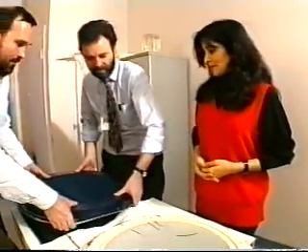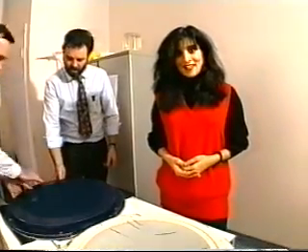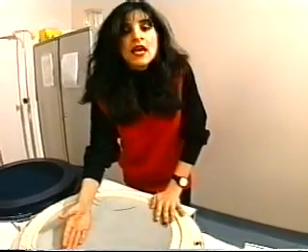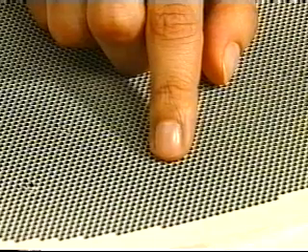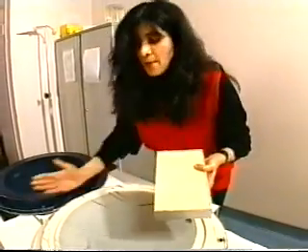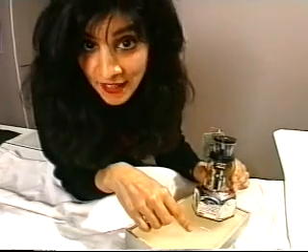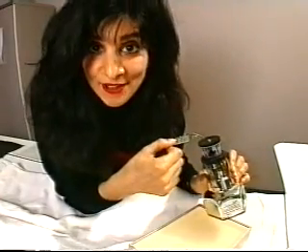These are the collimators. As you can see, they're extremely heavy. They are used to absorb the gamma rays which come in at an angle, except for those which travel at a right angle and pass straight through these tiny holes and hit a crystal — which is rather like this, except much larger. When the gamma rays hit the crystal, they produce a tiny flash of light, which is picked up by a photomultiplier and amplified to produce an electrical signal.